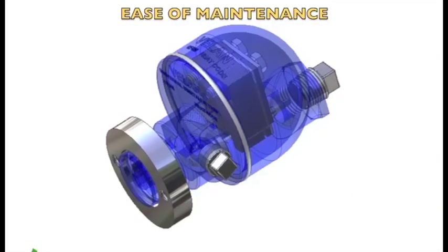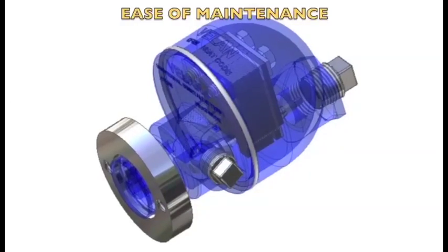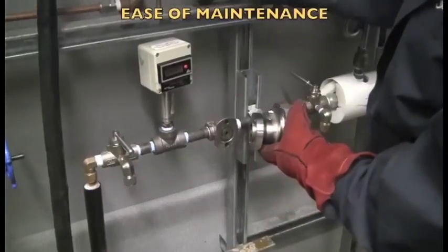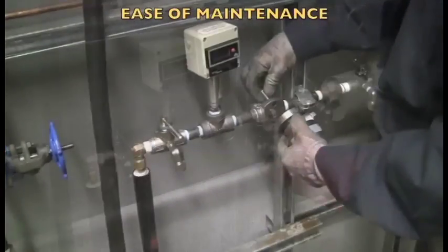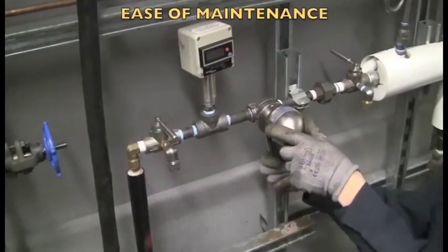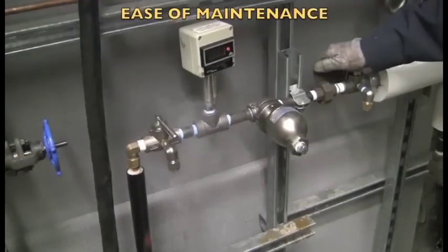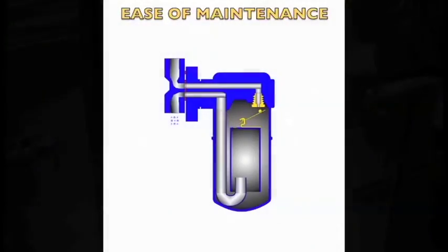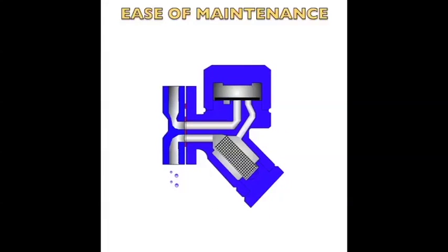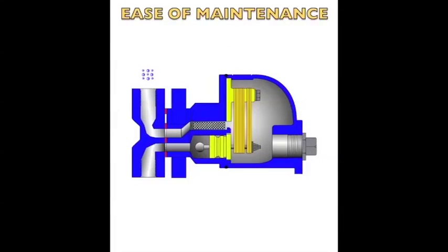Velan steam traps are also manufactured in the popular 2-bolt flange or universal connector body style. To renew the trap, simply remove the bolts holding the operating part to the pipeline connector and replace with a new unit. Velan universal connector traps are interchangeable with all other brands of pipeline connectors. This allows for easy replacement of conventional steam traps with the high-efficiency Velan steam trap.